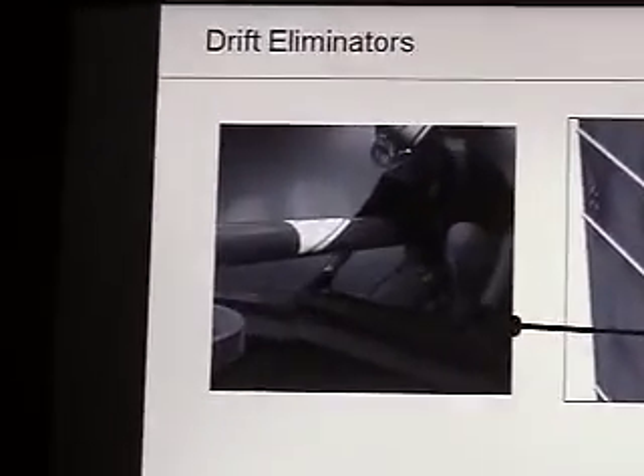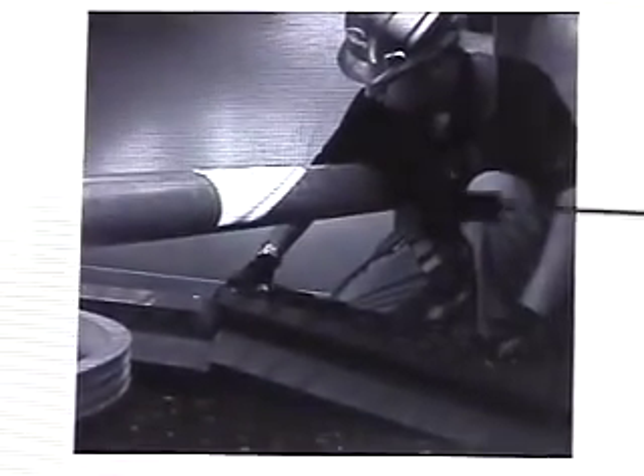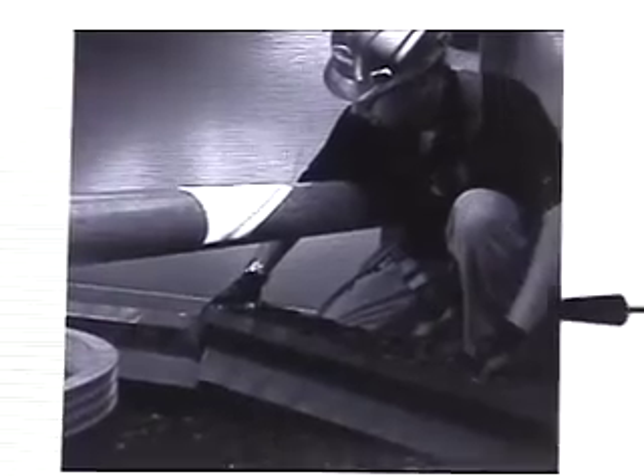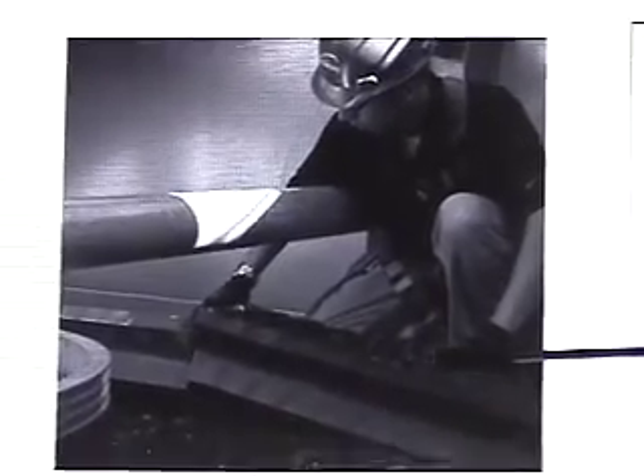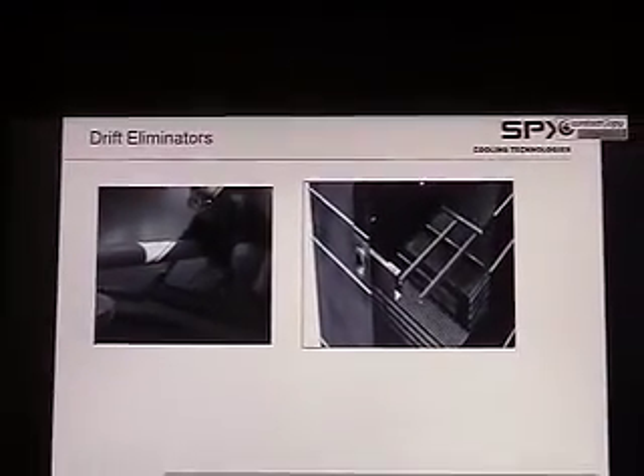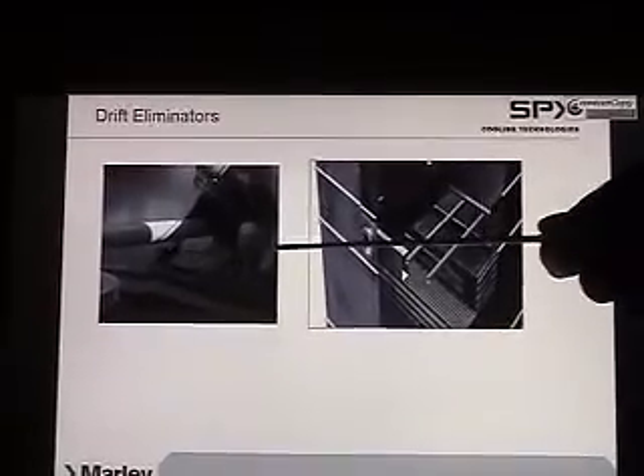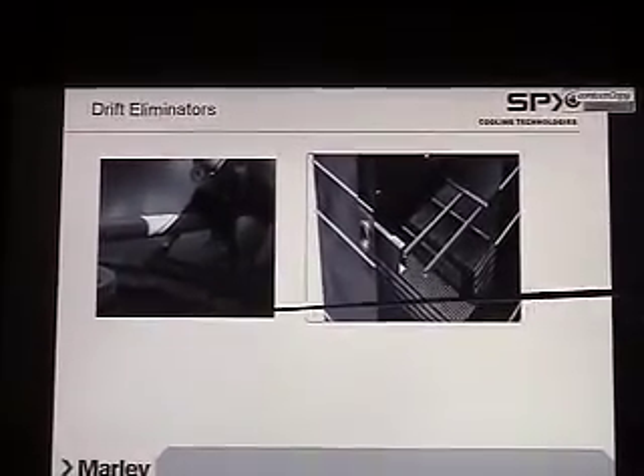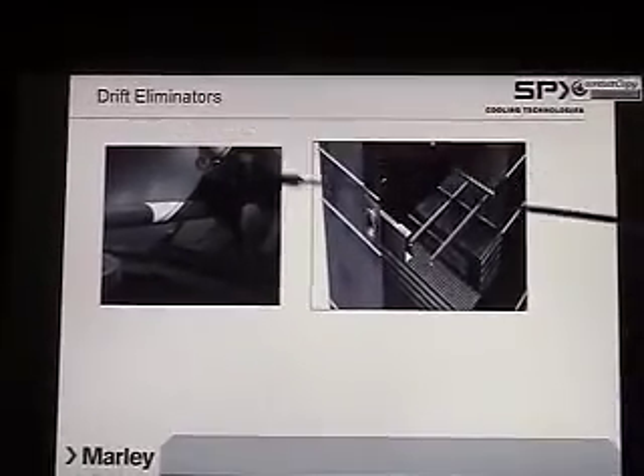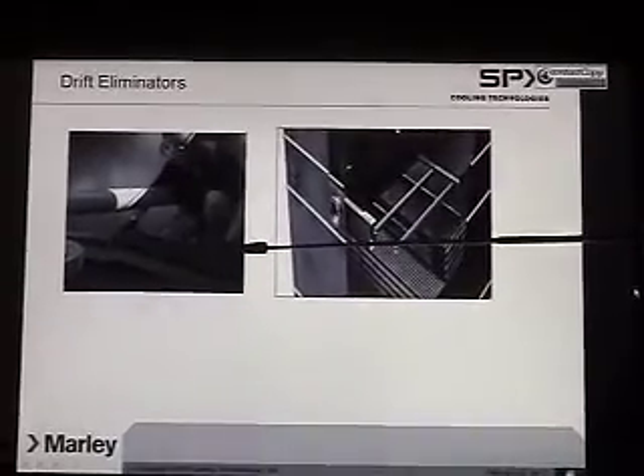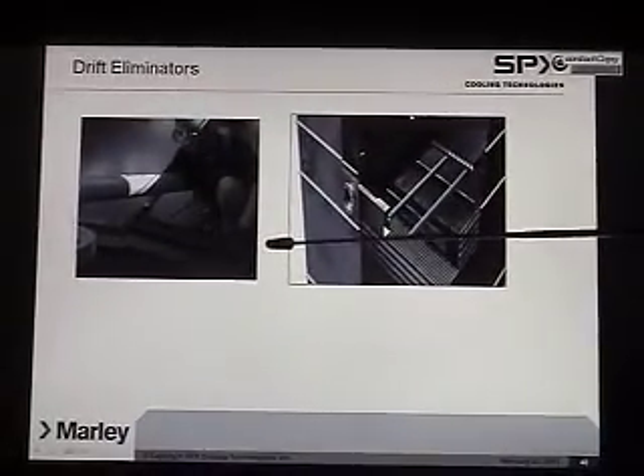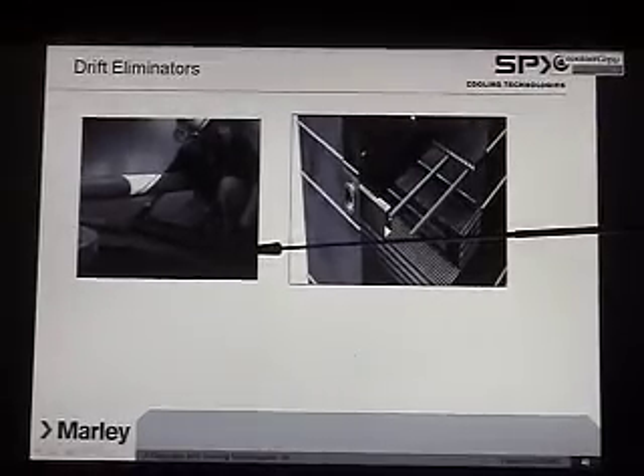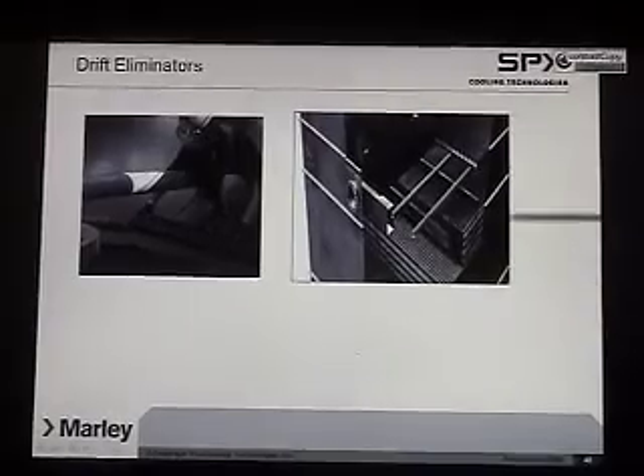This is actually someone removing one of those drift eliminator packs. He probably had to put a board down to distribute his weight, and then they just lift out, and they just fit together tightly, and that's how they stay in place. If you have rain around the tower and it's not raining, then it may be that you have a leak or a hole in your drift eliminator so that the water can escape up through the tower. The drift eliminators just simply capture that tiny amount of water droplets that are encased in the plume and go out the top of the tower.